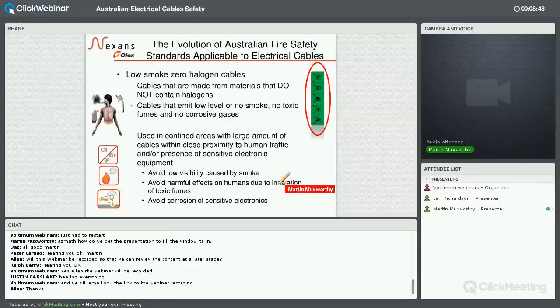Moving on from flame propagation, that second element which is important in fire-rated cables is that of the smoke that cables produce when they burn. For fire-rated cables, we typically look for zero halogen content and low smoke materials. So the materials will not contain any PVC, for example, which has chlorine in it. It won't contain chlorine or fluorine or any of those halogens. And the problem with the halogens is that any material that's got a halogen in it, when it burns, tends to produce lots of smoke and also corrosive gases, which you want to avoid, so that you prevent damage to sensitive electronics and so on.